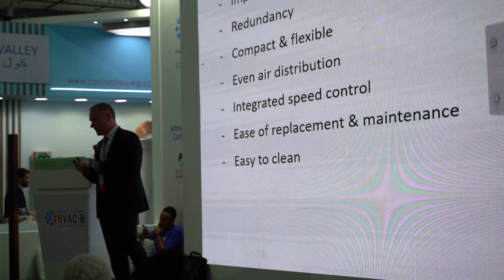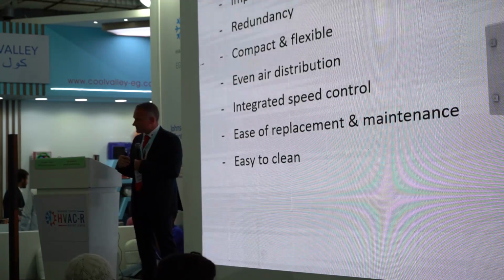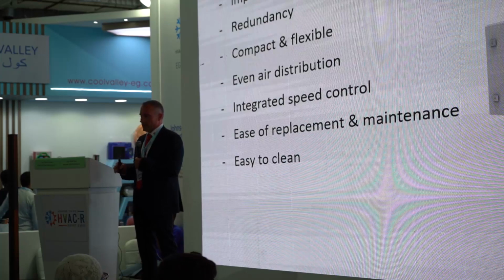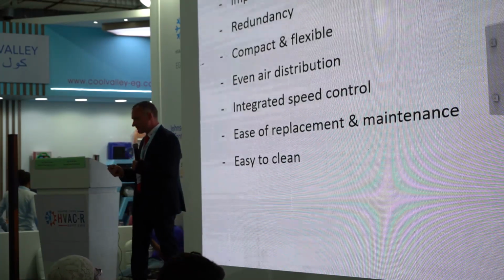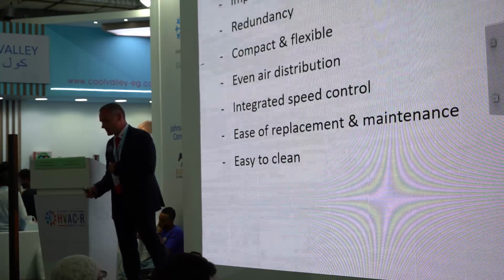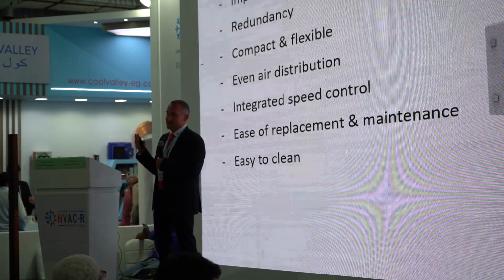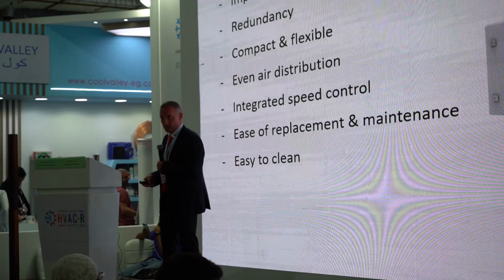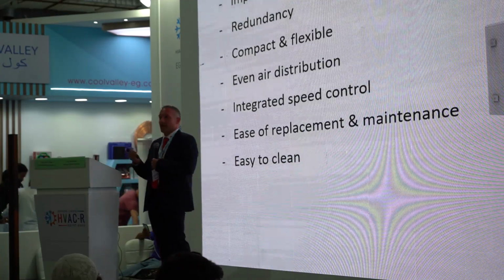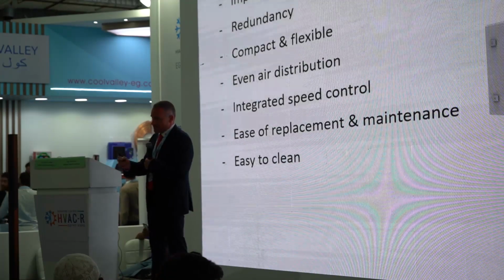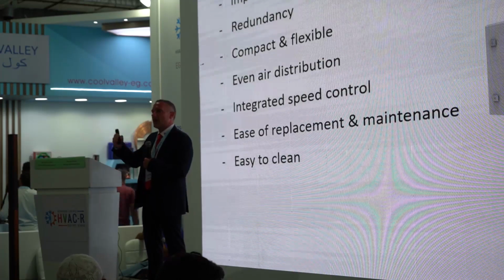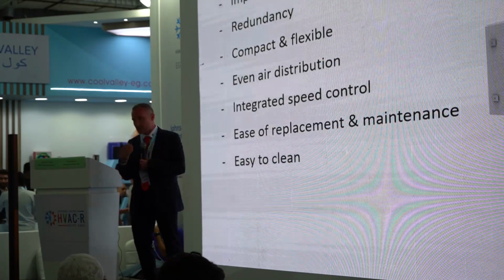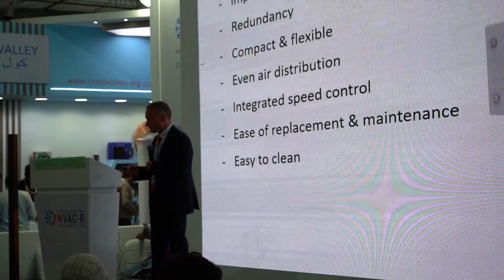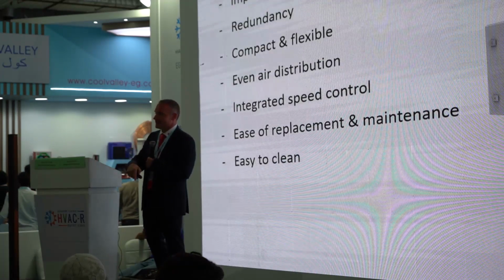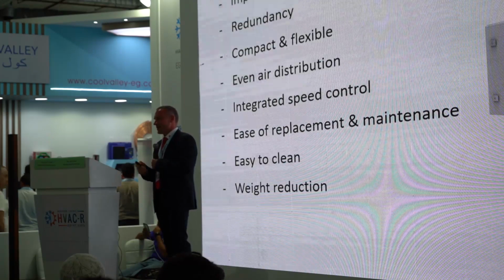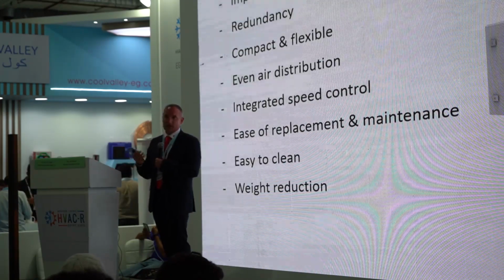There's no abrasive from a belt. It's clean inside, and you have total access to the floor, to everything. Remember the pictures of the belt-driven fan? There's a steel construction, there are dampers, and it's not easy to clean. If you think about sensitive areas like hospitals or the chemical industry, with the EC fan grid, no problem. It's clean, there's no belt abrasive, nothing. And if there's no abrasive, you don't even need the filter behind the fan, because this unit doesn't create any dust, any particles, nothing. Reducing the filter also means reducing the needed pressure. There's also weight reduction of the whole unit, and of course you save a lot of space.